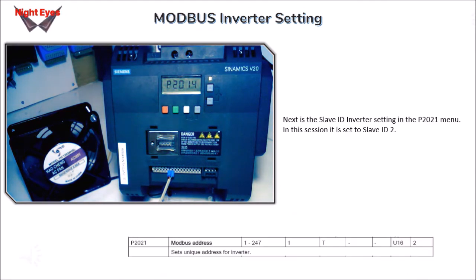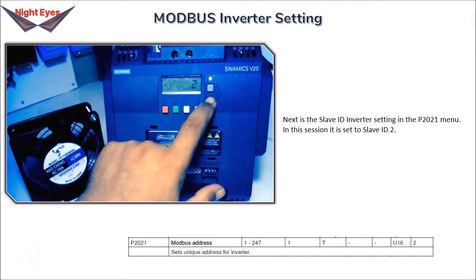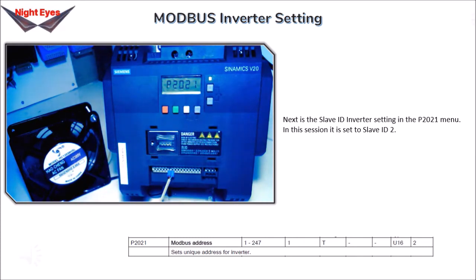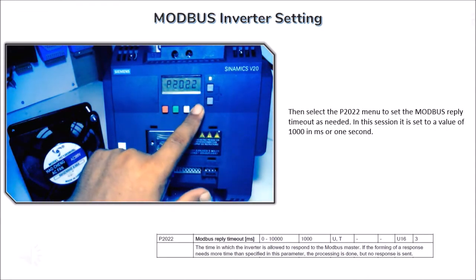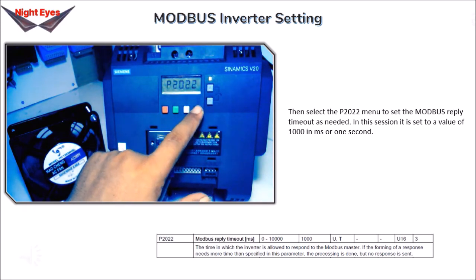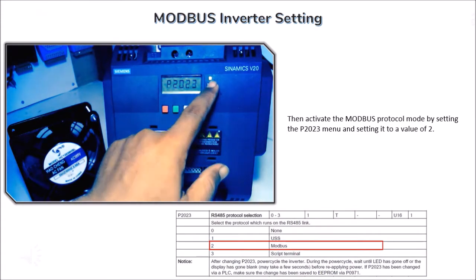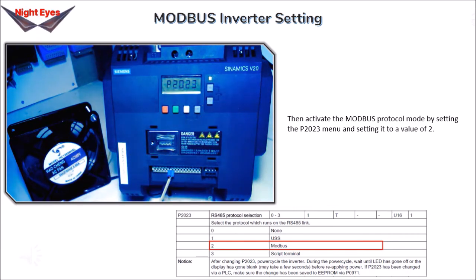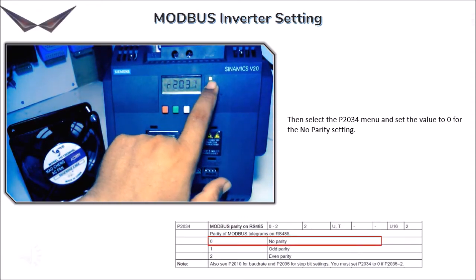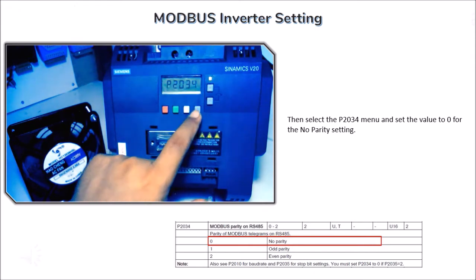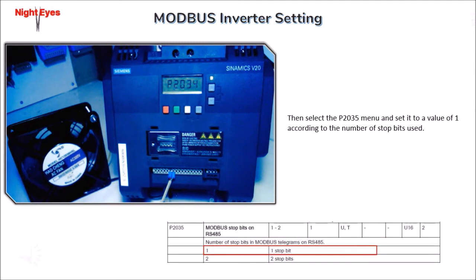Next is the Slave ID setting in the P2021 menu — in this session it is set to Slave ID 2. Then select the P2022 menu to set the Modbus reply timeout; in this session it is set to 1000 milliseconds or 1 second. Activate Modbus protocol mode by setting P2023 to a value of 2. Select P2034 and set it to 0 for No Parity. Then select P2035 and set it to 1 according to the number of stop bits used.